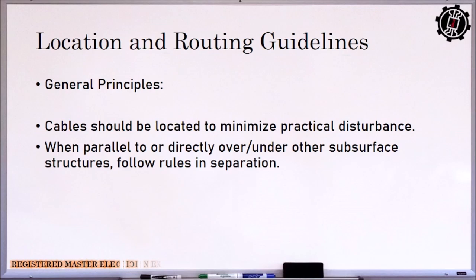Then in installation, so install cable in straight and direct line as practical. So hangga't maaari dapat yung ating cable which is direct buried or does not run on a conduit system, dapat it must be on straight line, no? As practical, no? As long as pwede siya i-straight line, so do it on straight line. If hindi naman, so bending radius when required should be sufficiently large to prevent damage to cable. So dapat kung ano yung nakalagay na bending radius for that specific cable, so mas mainam na yun yung sundin or mas mainam pa talaga nga mas higit pa doon sa bending radius.